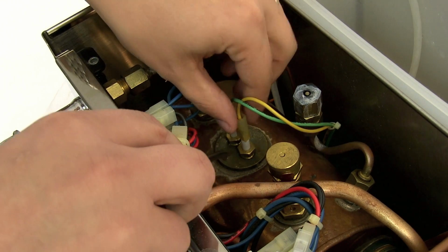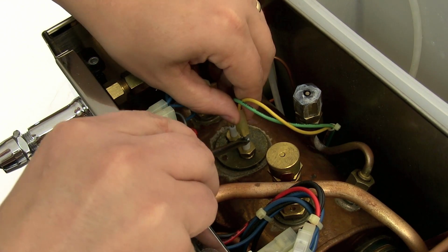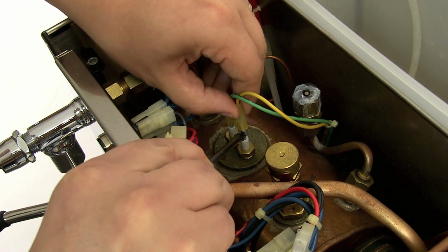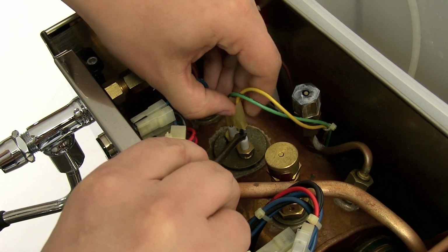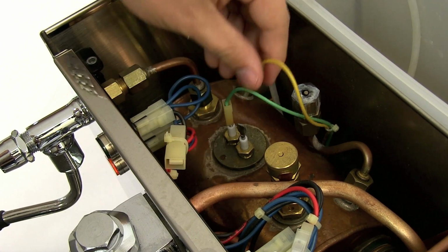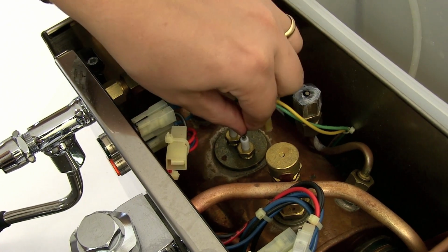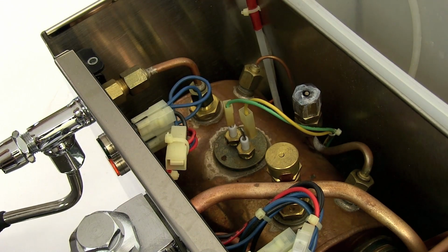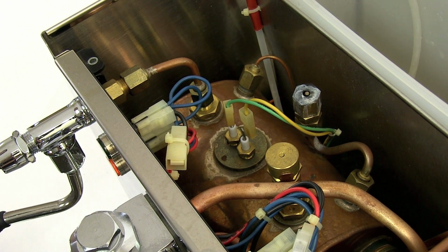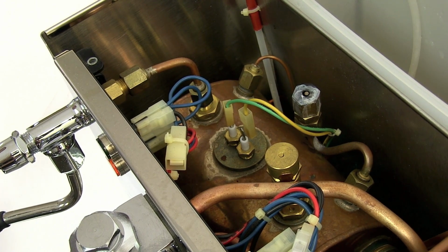And what I'm going to do, I'm just going to remove this. Now what's happening here is I'm also pulling out the probe, but I've taken off the header there essentially, and I'm going to push that probe back in. And now, once I turn the machine on, it's not going to sense water and it will overfill the boiler.